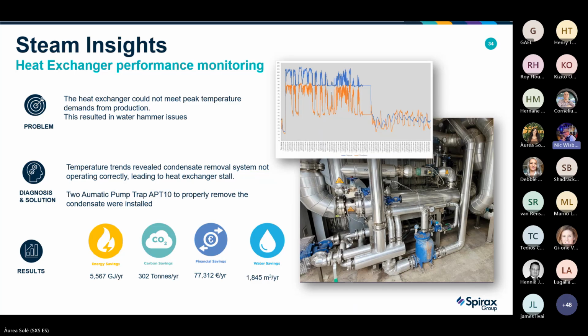And by doing that, we can extrapolate the costs, so how much that heat exchanger is actually costing you to run. For instance, there's an example at the bottom middle part of the slide telling you the energy savings from making sure that heat exchanger is running efficiently, how many tons per year you're saving by making sure it doesn't enter into flood, and the financial costs. That's in euros, which is very similar to dollars. So you can see the savings that can be made.